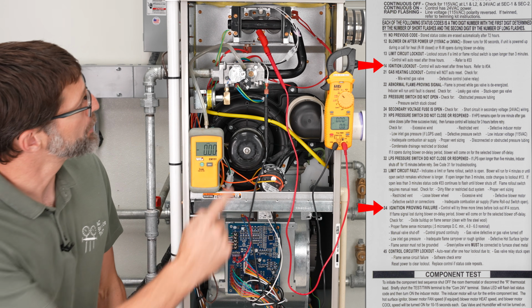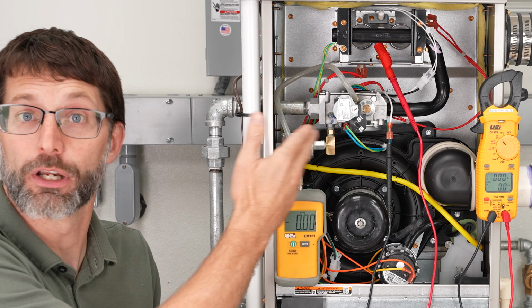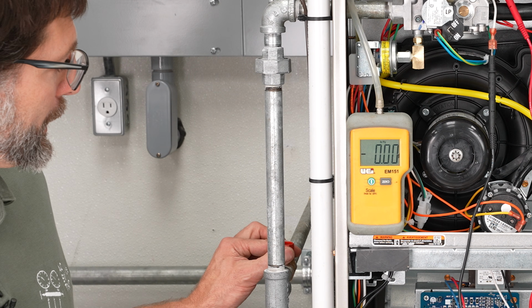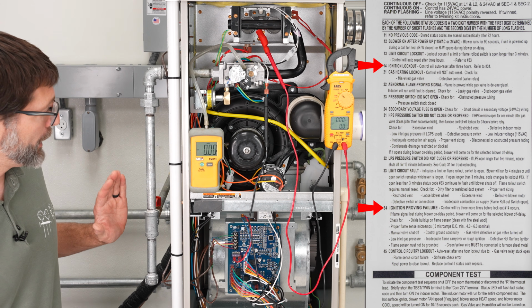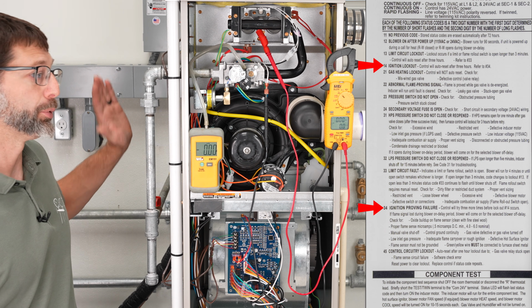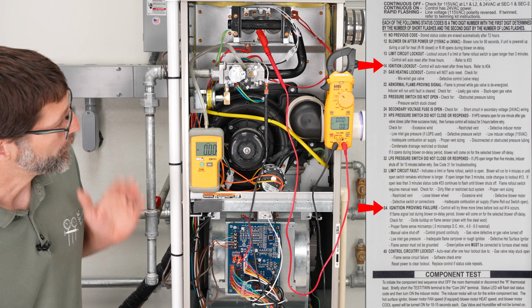And so you could have something as simple as this right here, where you have this switch in the off position, it needs to be turned on. You could have your gas valve, it could be shut off and it needs to be turned on. You could have maybe your natural gas or your propane off outside, so at the meter. So that could be an issue.